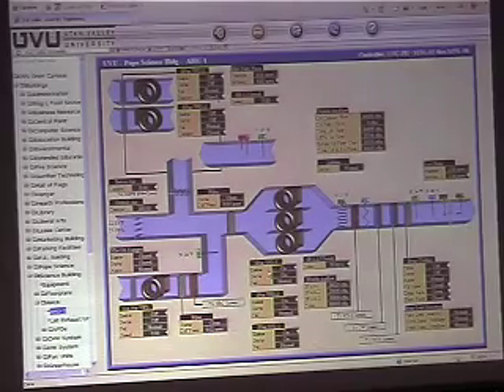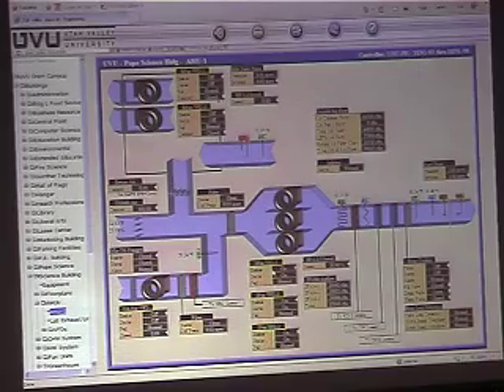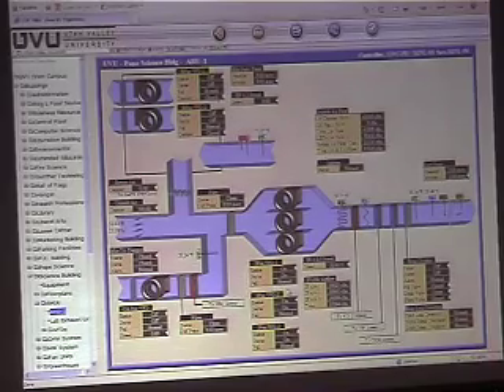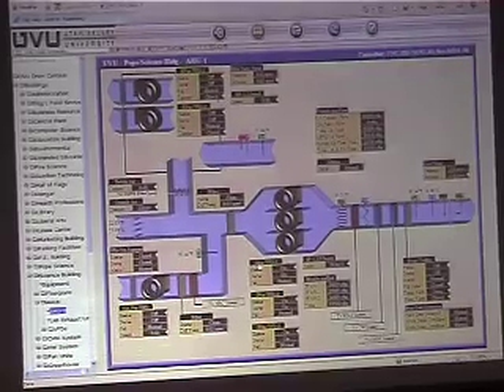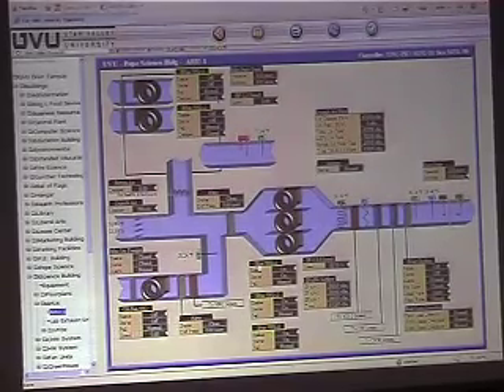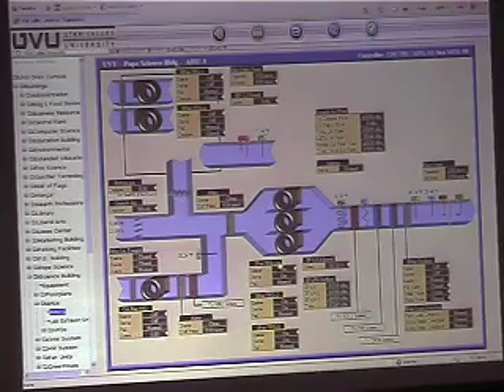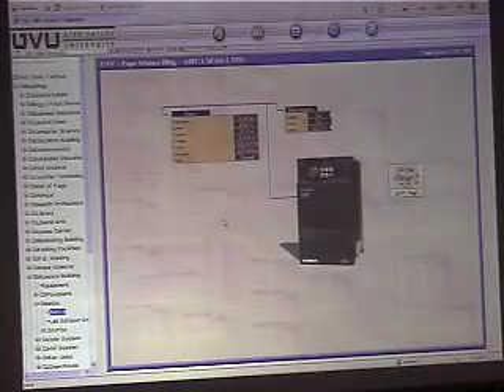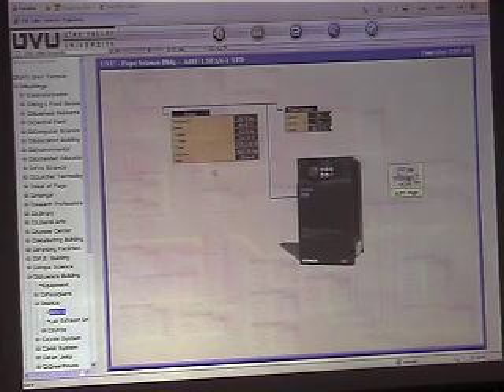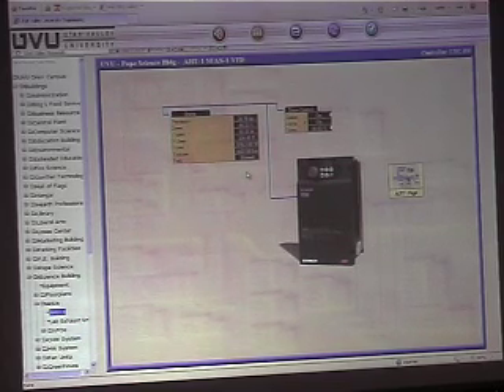Your fan controls shown here. Each supply fan has its own VFD. So there's an enable, its status, and whether or not there's an alarm condition here for that fan. We're also tied into these VFDs through a LAN interface. So there's a yellow highlighted box around these tags here to indicate that there's a link there you can click on. So if you click on that, it'll take you to the screen that has the VFD on it, and it'll show you the other values that we're monitoring through that interface. I've also added here, just as redundancy, what's on the air handler screen as far as our physical points, so your enable, your status, and your speed.